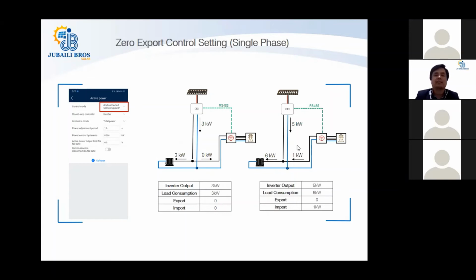In a case where the power requirement of the load side is more than the generation capacity of your inverters, the excess power required will be taken from the grid side. So these two pictures shown in this slide are a quick description of how this system works when you have a single phase scenario and you are doing the zero export control.